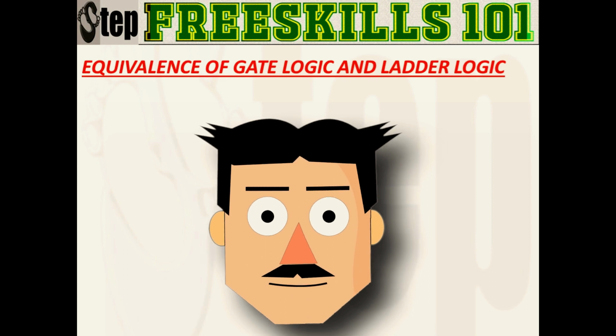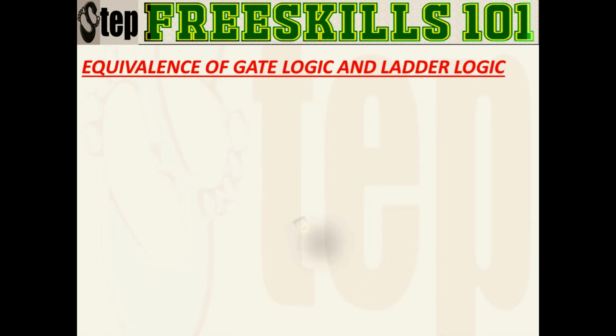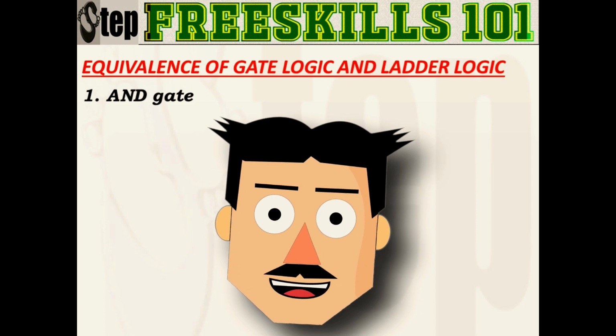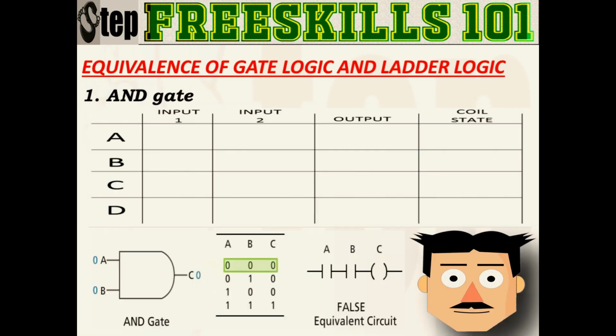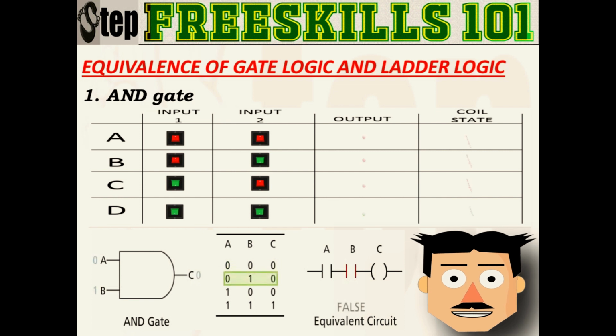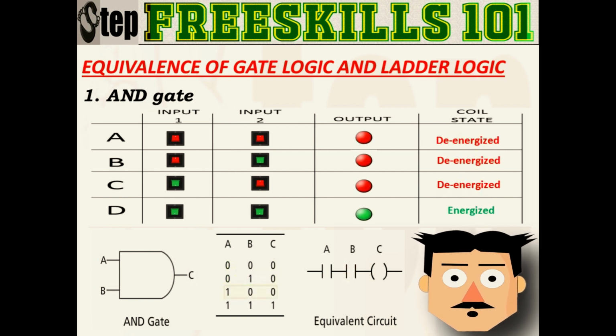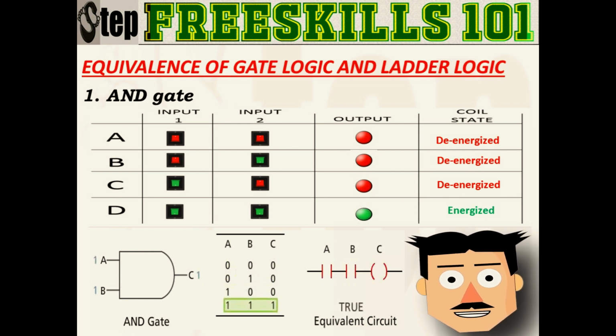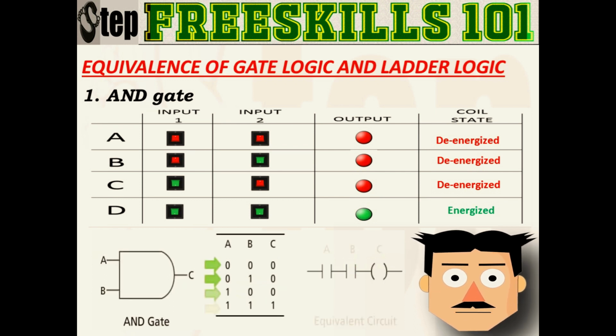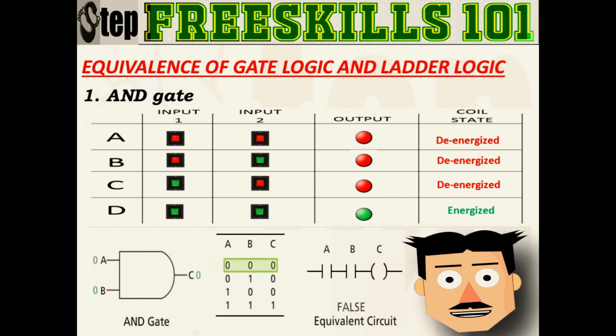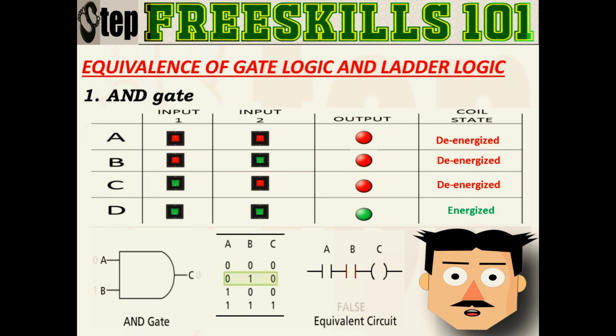Equivalence of gate logic to ladder logic. One, AND gate. Both or all inputs must be in the on state in order to produce a true and on outcome. This is used where both conditions must be satisfied to output a true or on state. For example, you need to set both the power and start buttons in order to run the motor.